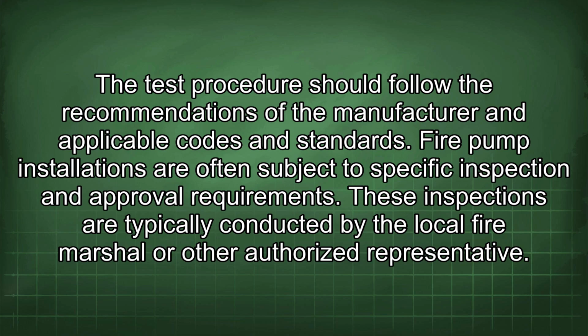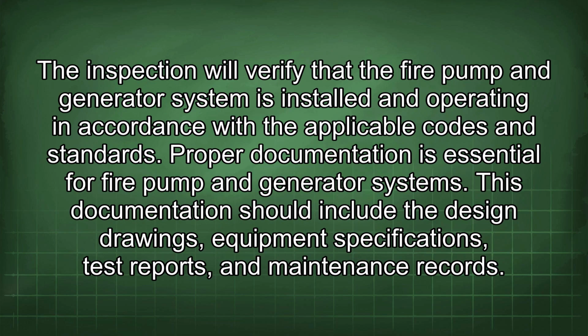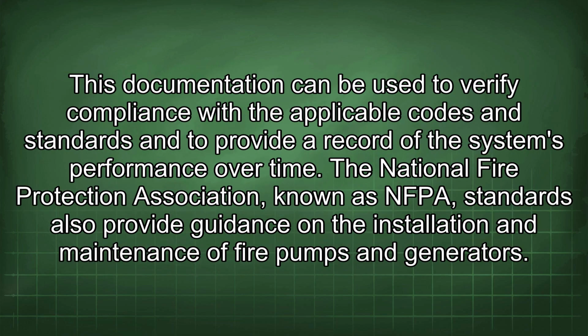Fire pump installations are often subject to specific inspection and approval requirements. These inspections are typically conducted by the local fire marshal or other authorized representative. The inspection will verify that the fire pump and generator system is installed and operating in accordance with the applicable codes and standards. Proper documentation is essential for fire pump and generator systems. This documentation should include the design drawings, equipment specifications, test reports, and maintenance records. This documentation can be used to verify compliance with the applicable codes and standards and to provide a record of the system's performance over time.